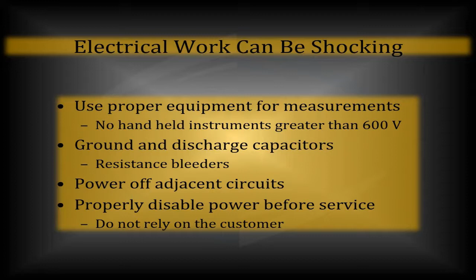Properly disable power before you're working on this stuff. And by properly disabling it, do it yourself. Never send a customer down to shut off a breaker or a blade or knife switch or anything like that. Always do it yourself and use your lockout, tagout lock that's properly tagged and filled out so that you can be the only one that's going to remove that and you know exactly what's turned off.